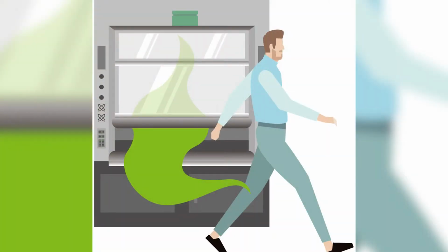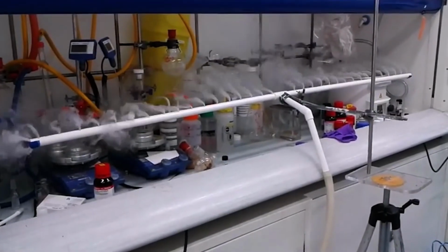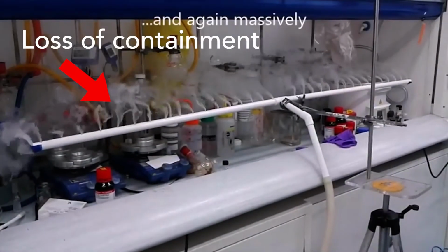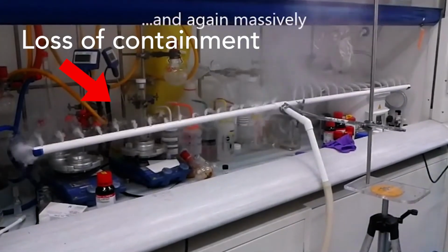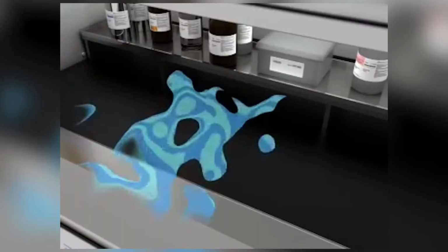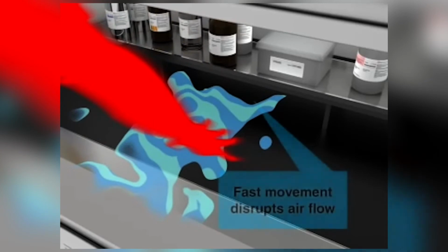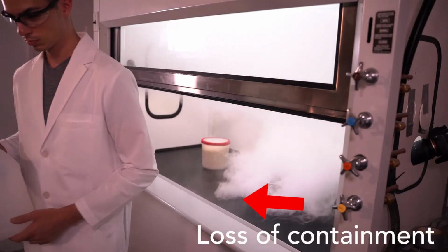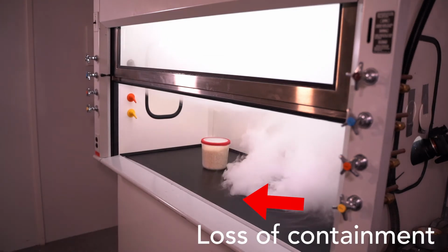Now, walk past the hood with an open sash. That low pressure area is now behind you. As you walk by, it can suck chemicals out of the hood. Also, if you move your hands in a fast manner inside the hood or quickly remove objects from the hood, you can draw chemicals out. All these events are loss of containment. The fugitive chemicals can be inhaled by those at the hood, and they also pollute the air in the lab.